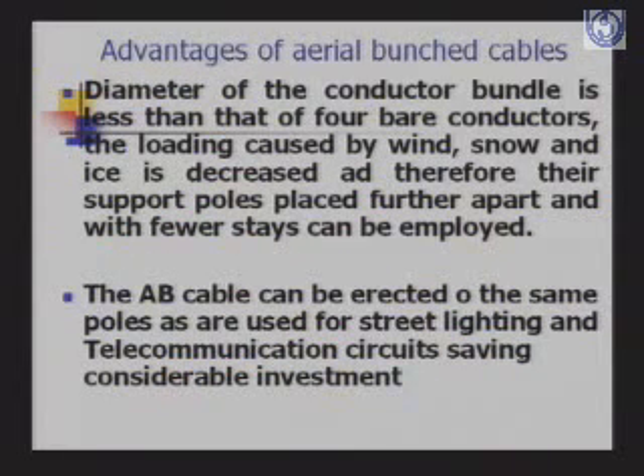The advantages of aerial bunched cables are that the diameter of the conductor bundle is less than that of 4 bare conductors. The loading caused by wind, snow and ice is decreased, and therefore their support poles can be placed further apart and fewer stays can be employed. The aerial bunched cable can be erected on the same poles as are used for street lighting and telecommunication circuits, saving considerable investment.